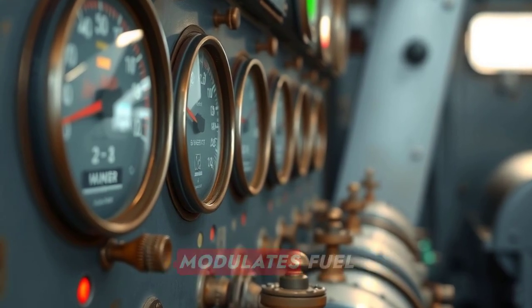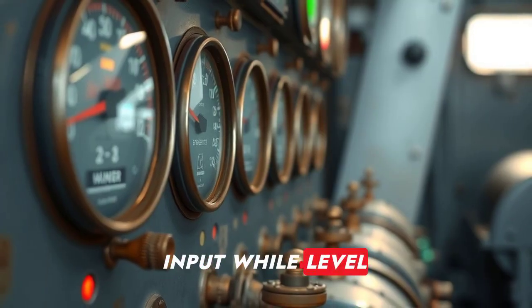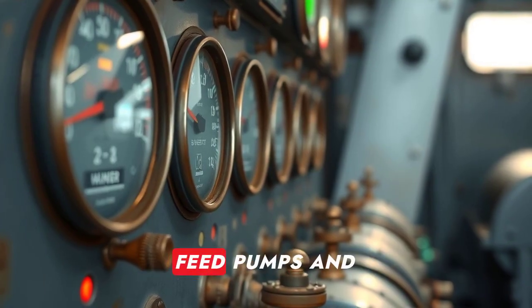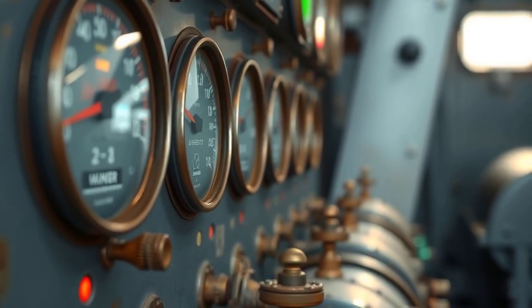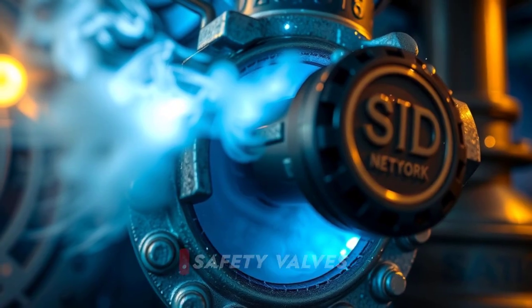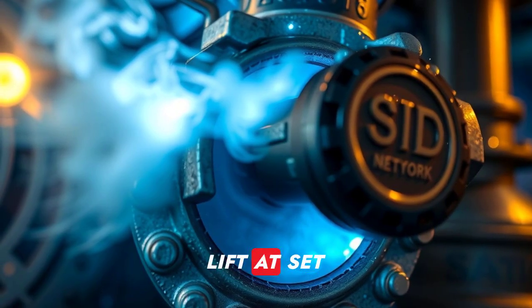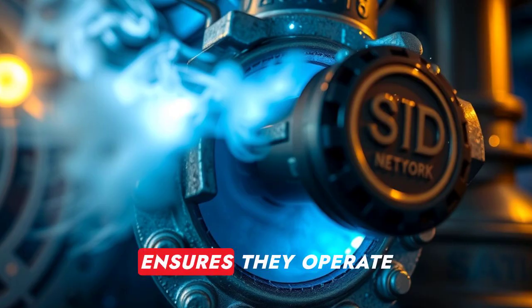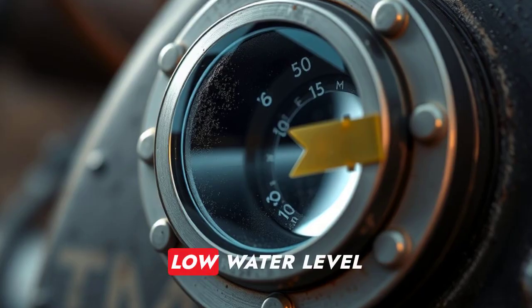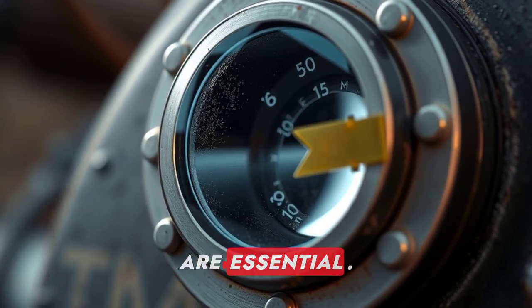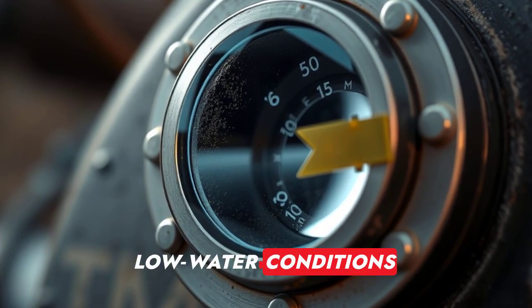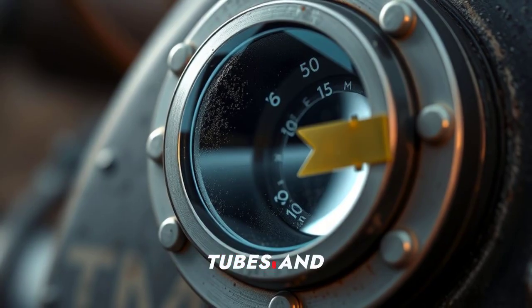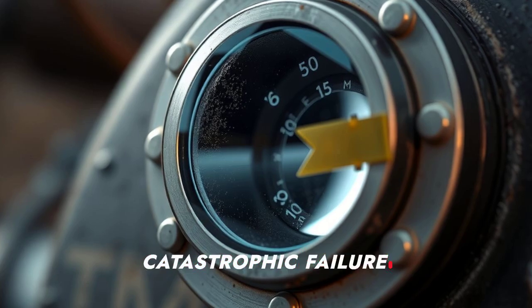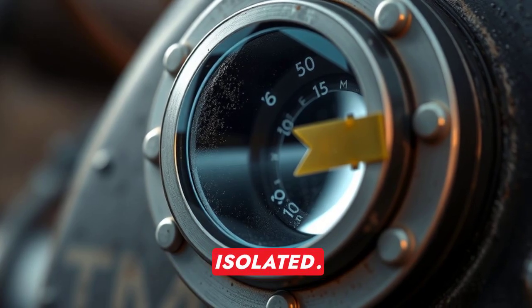A pressure controller modulates fuel input, while level controllers operate feed pumps and valves. Key safety device. Safety valves lift at set pressure to prevent overpressure. Regular testing ensures they operate reliably under load conditions. Low water level alarms and trips are essential. Low water conditions risk overheating tubes and catastrophic failure if not automatically isolated.